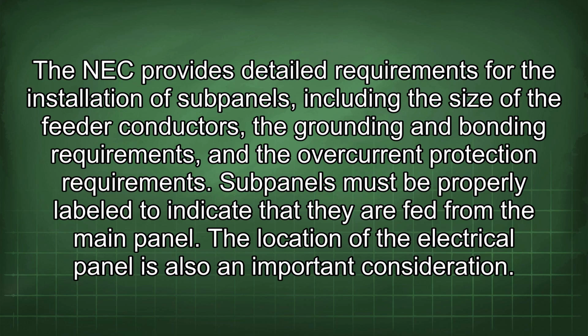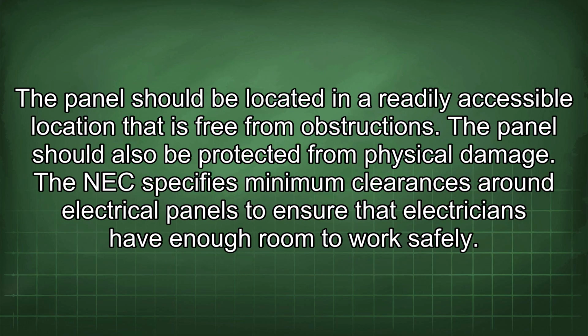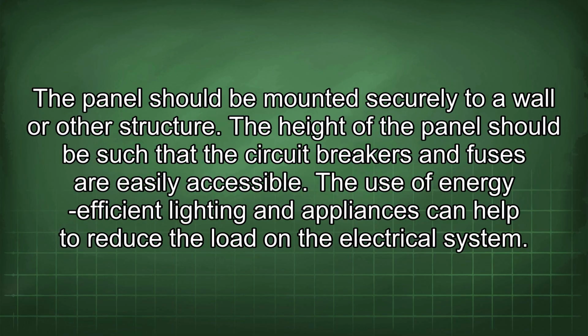The location of the electrical panel is also an important consideration. The panel should be located in a readily accessible location that is free from obstructions. The panel should also be protected from physical damage. The NEC specifies minimum clearances around electrical panels to ensure that electricians have enough room to work safely. The panel should be mounted securely to a wall or other structure. The height of the panel should be such that the circuit breakers and fuses are easily accessible.